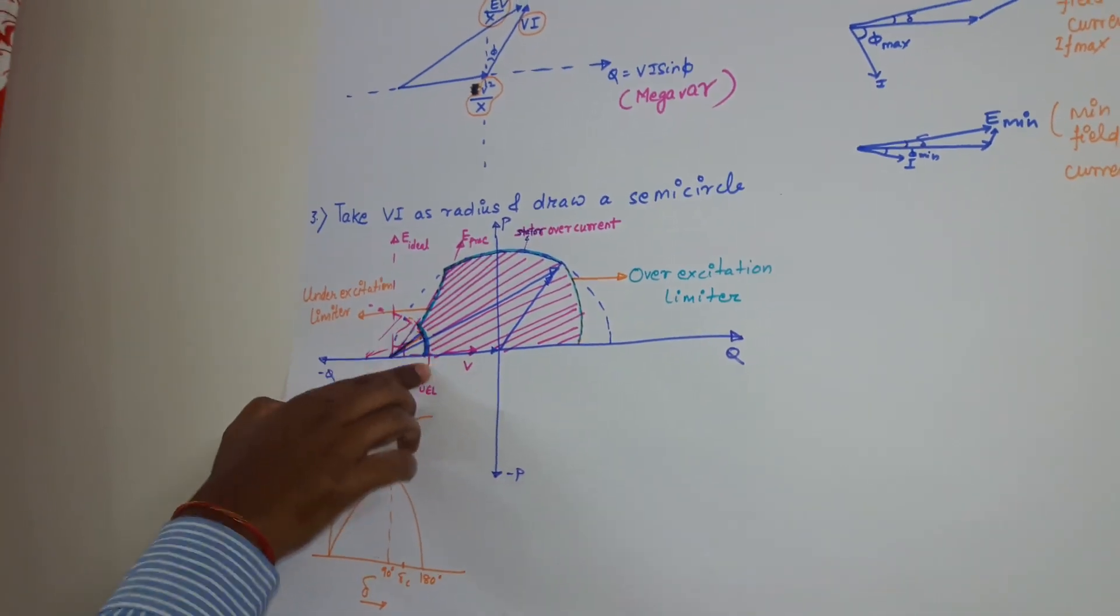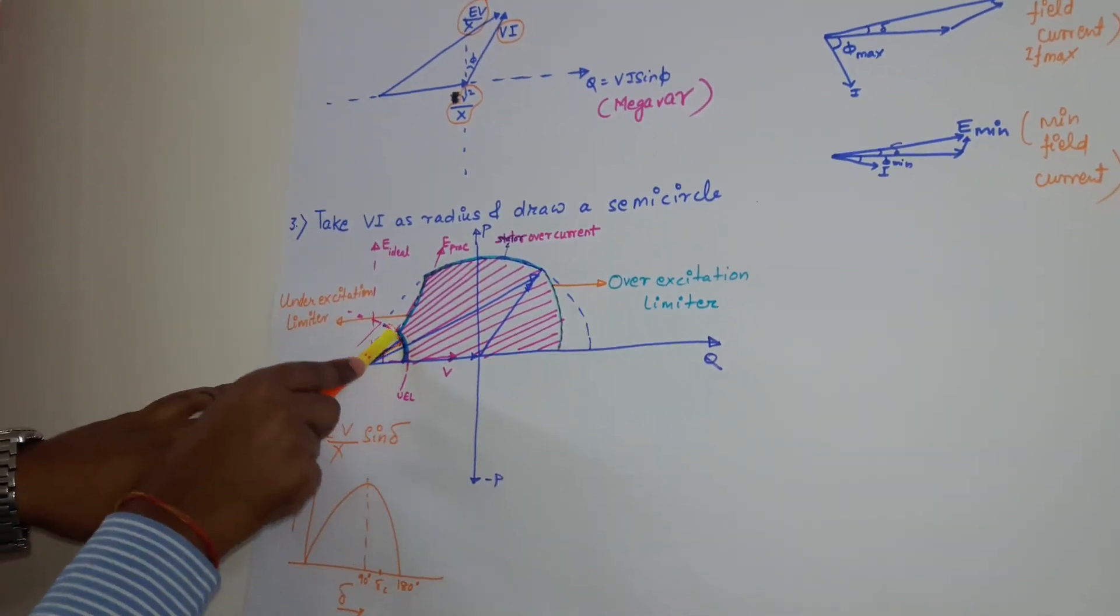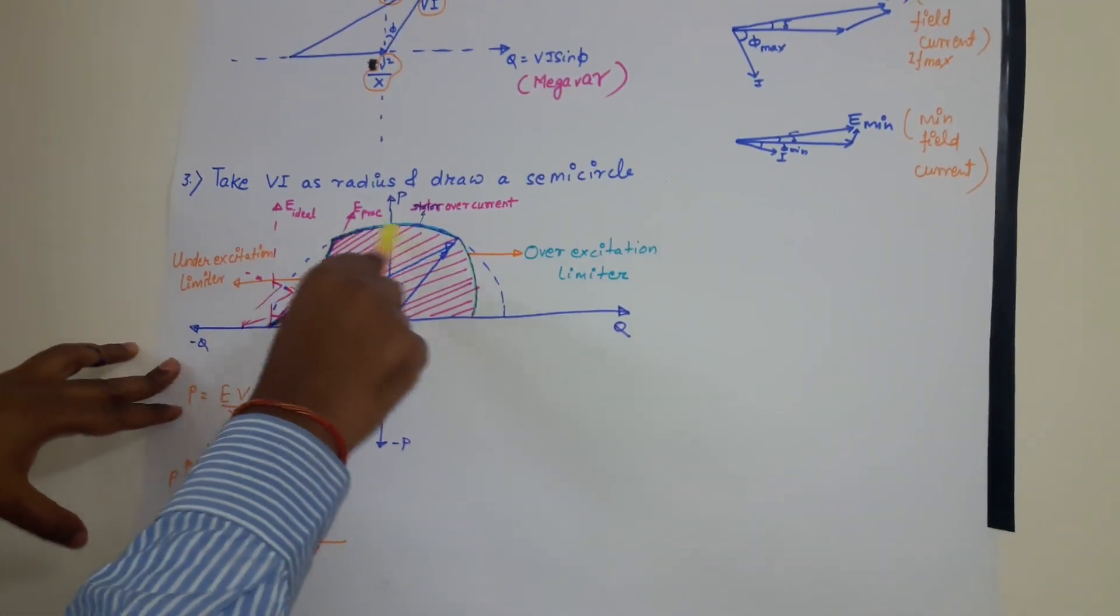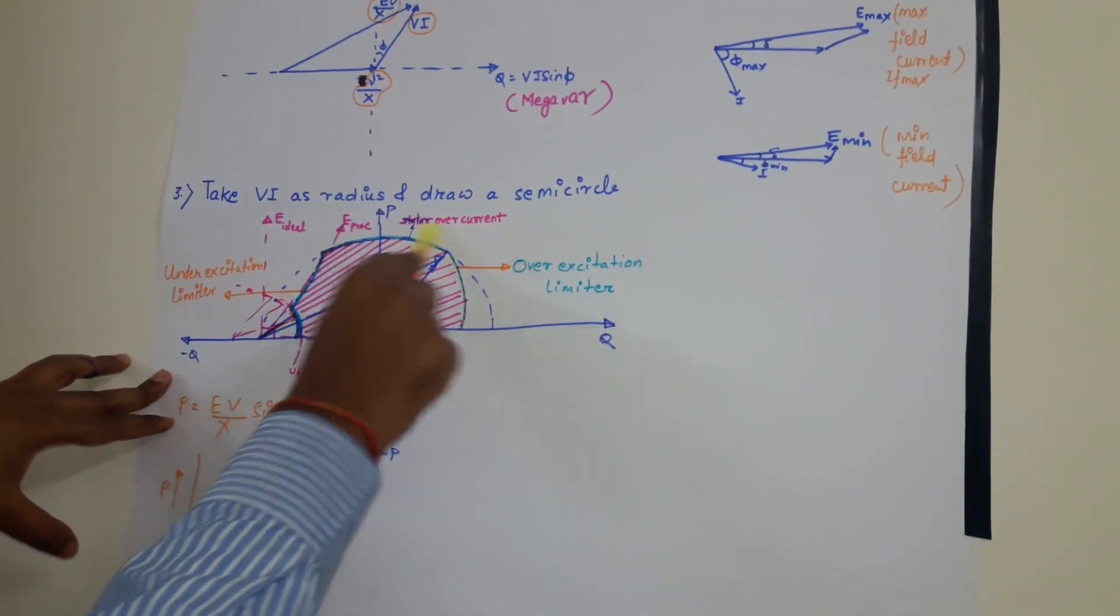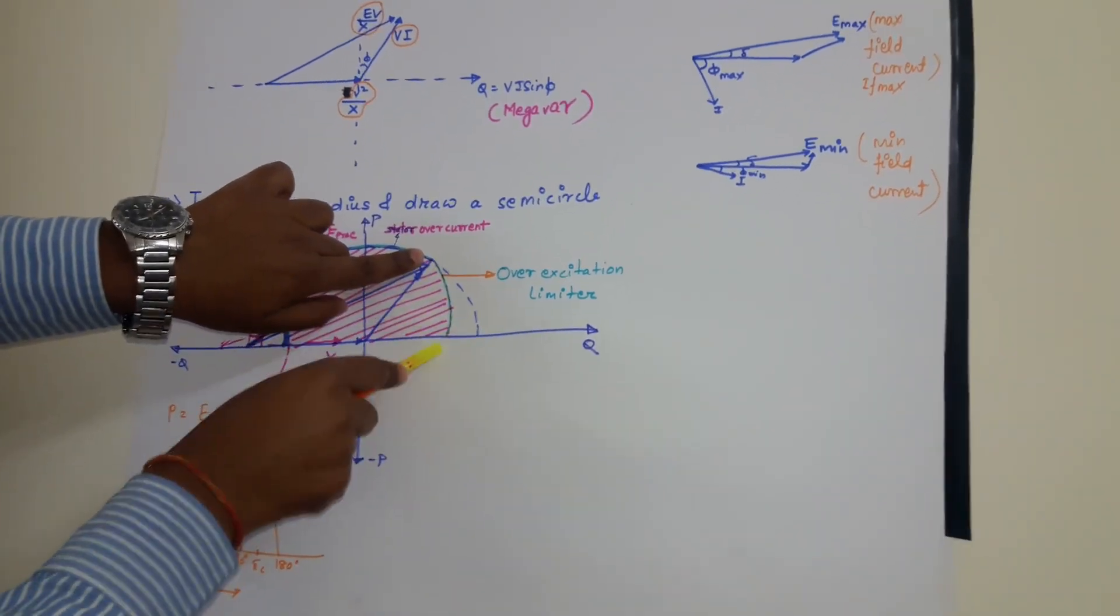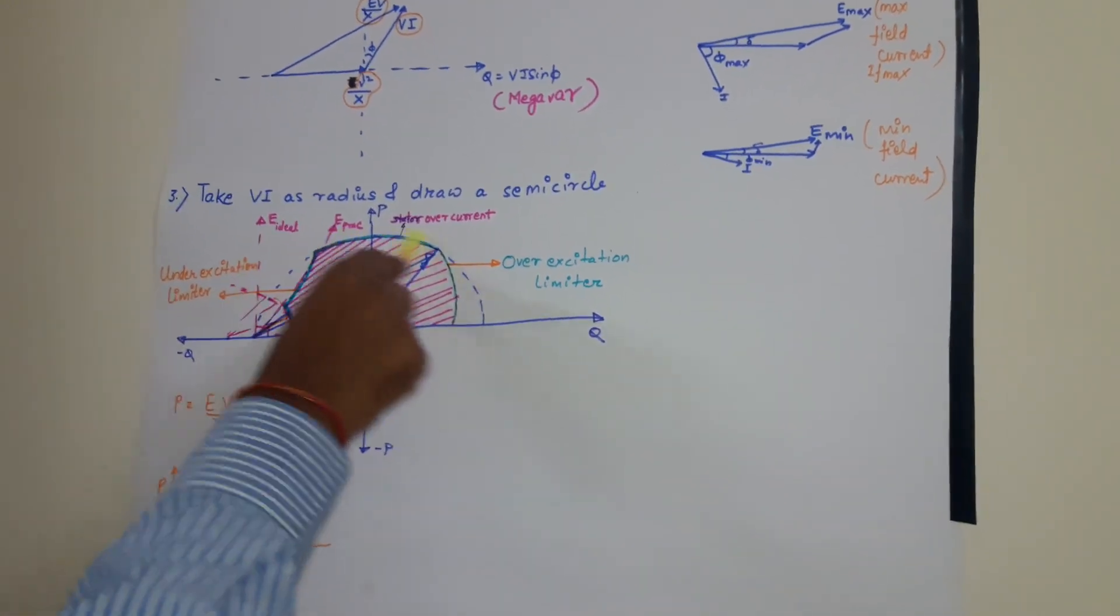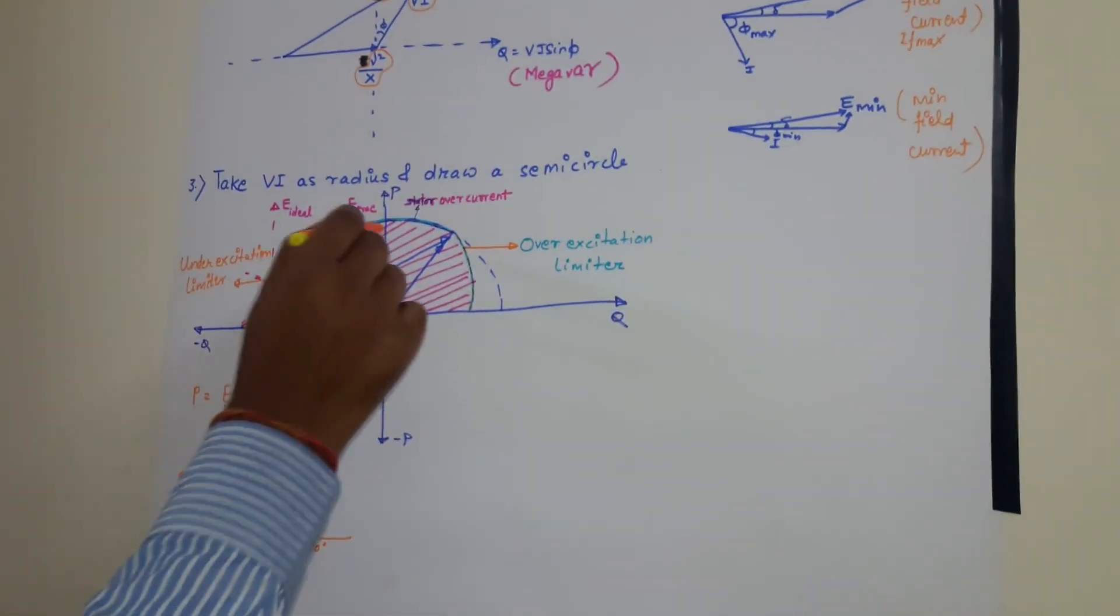So finally what we are getting, a curve like this, then like this. Then this is my full ability of generator of the load current, that is stator over current. And after that, the over excitation limiter like this. So the total zone is the capability curve of the generator, within which our generator can operate.